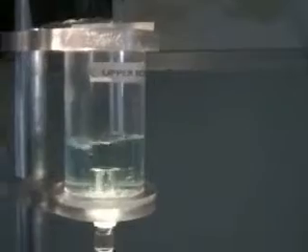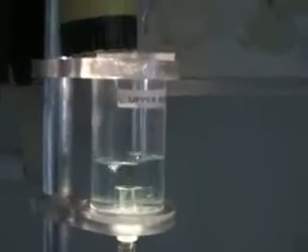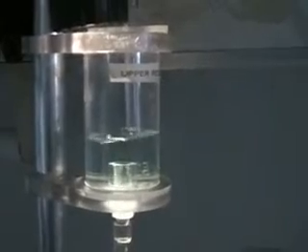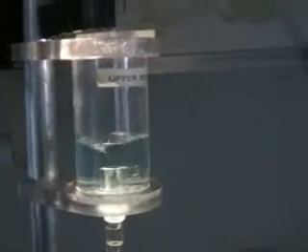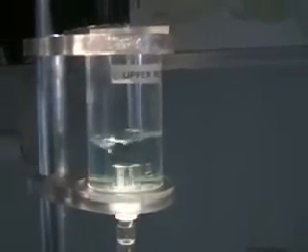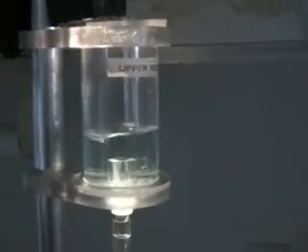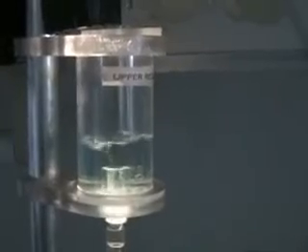So the baffles stop the rapid rotation of the fluid particles on the surface and inhibit the formation of vortexes. They could be vertical or horizontal. It depends a lot on the particular conditions of the tank and its shape.